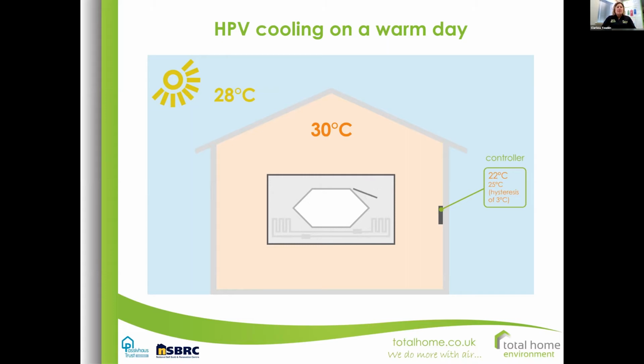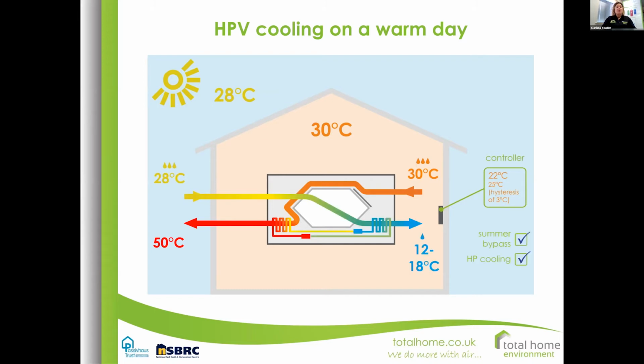So here you can see automatic summer bypass coming down, the airflow being extracted out of kitchens and bathrooms. It doesn't go through the heat recovery matrix. It goes past the heat pump. Fresh air is drawn from outside and goes through the cold side of the heat pump. And hey presto, all very energy efficient cooling going on here, with the automatic summer bypass doing the work first.